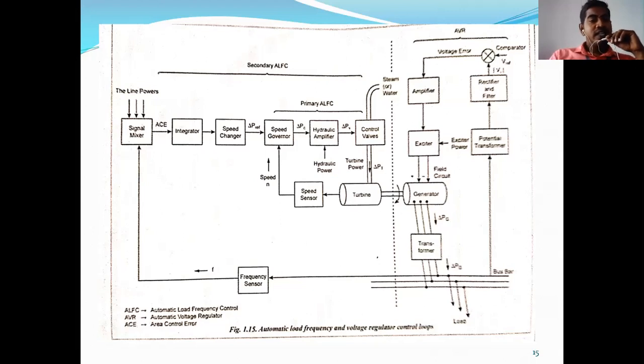The signal mixer output is given to the integrator, which integrates the signals from the signal mixer and frequency sensors. Both signals are integrated and given to the speed changer. Based on the input from the integrator, the speed changer gives a command to the speed governor, which controls the valve of the turbine.